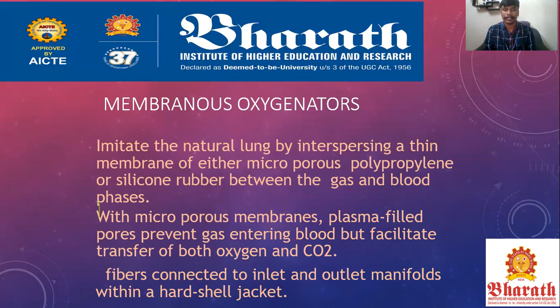With microporous membranes, plasma-filled pores prevent gas from entering the blood directly, but facilitate the transfer of both oxygen and CO2. Through the pores, O2 will be embedded and CO2 will be removed. Fibers are connected to the inlet and outlet within a shell jacket, and this type is known as the membranous oxygenator. Next one is the bubble oxygenator. The membranous oxygenator is an exact replica of the natural lung, where through the micropores gas molecules are embedded and CO2 is removed.